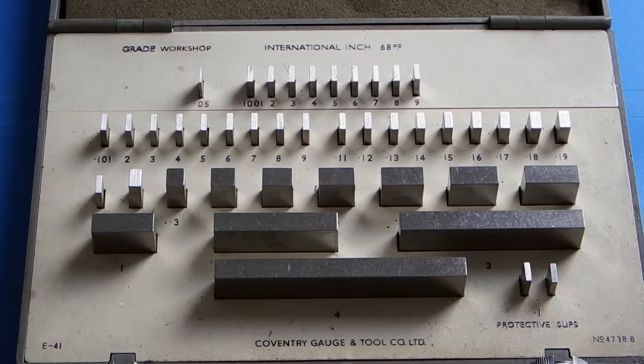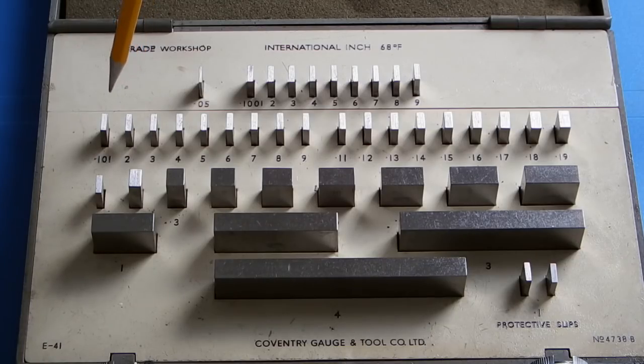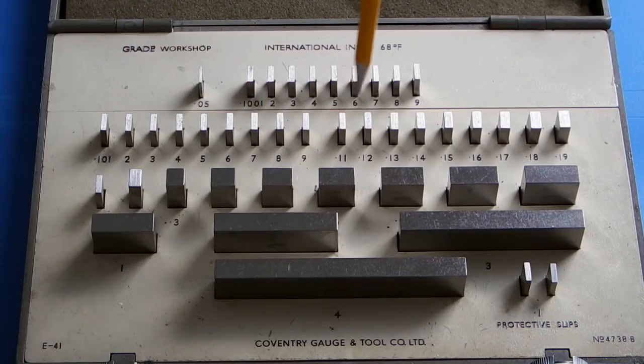Now the correct size might not be what's on the block here, but it should be related back to the calibration certificate that came with the blocks. On that certificate you'll have the size that the block should be and the size that the block actually is at 68 degrees Fahrenheit.